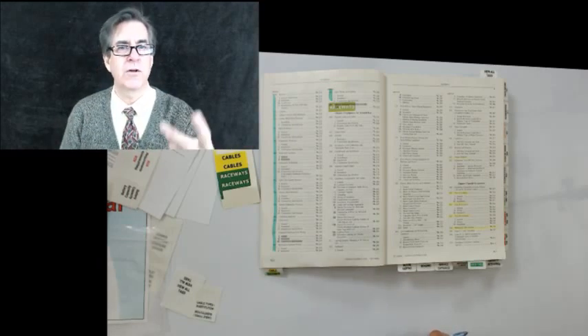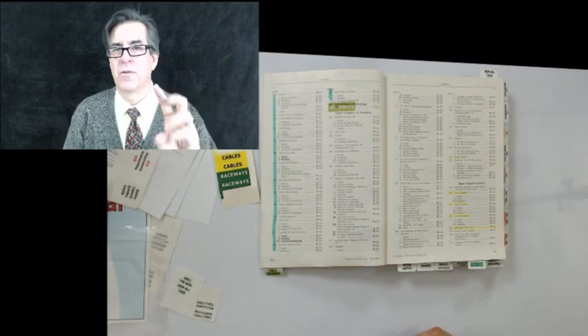It's class 1, class 2, class 3, Roman numerals, okay? Not number 1, 2, and 3. Because class 1, class 2, class 3 are different from remote control, signaling power, and limited circuits, which are number 1, 2, and 3.